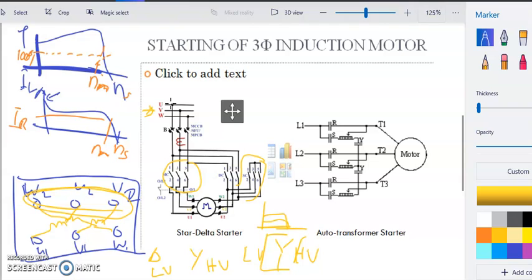Once the motor runs, we disconnect here, and we disconnect this one, but we connect this one and this line. So it becomes delta. First we start with star, or Y connected, then we continue with the normal delta connection. So we can have a low incoming current with the starting, then it continues with the normal current.